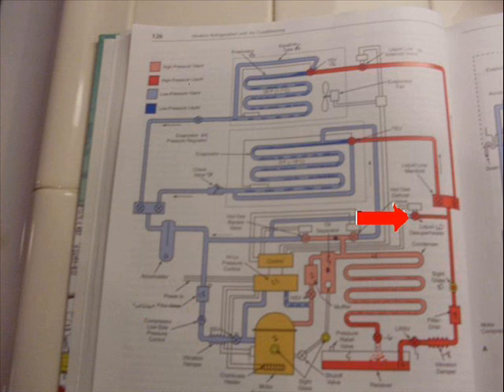The valve has a limiting orifice inside of it that puts out a spray. It does not send liquid in the line. It puts out a spray of droplets. This cooling fog runs back and cools the compressor motor. Liquid desuperheater.